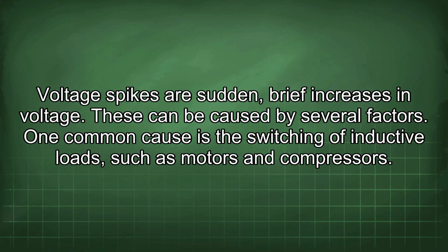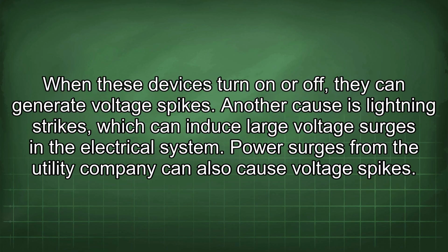Voltage spikes are sudden brief increases in voltage. These can be caused by several factors. One common cause is the switching of inductive loads, such as motors and compressors. When these devices turn on or off, they can generate voltage spikes. Another cause is lightning strikes, which can induce large voltage surges in the electrical system. Power surges from the utility company can also cause voltage spikes.